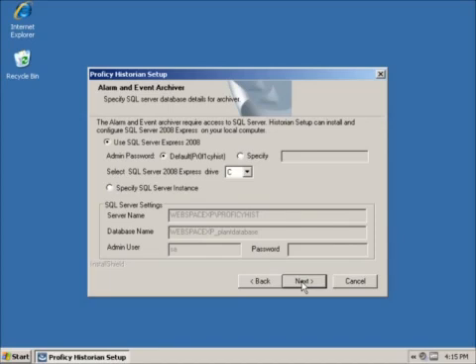The Alarm and Event Archiver requires a SQL database to store the collected alarms and events. If you do not have a SQL server, you can install SQL Server 2008 Express as part of the Historian setup. Be sure to record the SA password for the instance that you create. If you have an existing SQL Server, please consult with one of our application engineers for the additional requirements.